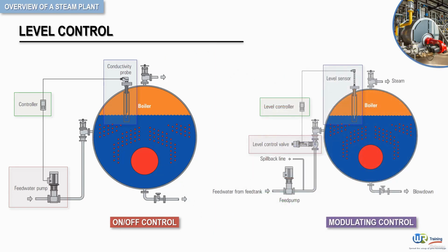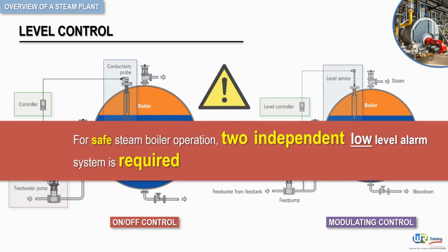Now, it is important to note here that for steam boiler safe operation, it is a legal requirement in most countries to have two independent low-level alarm systems.